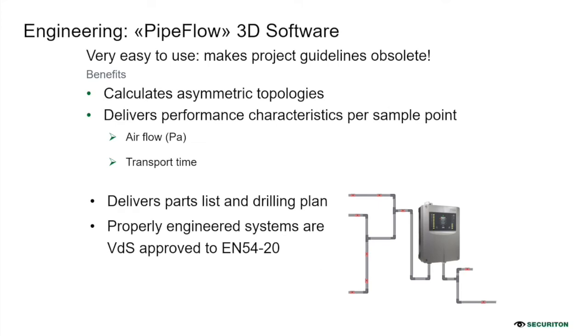During the question and answer session, you asked about software. We have software which calculates the pipe length, the airflow, transport time, number of holes and size of holes. Depending on the individual hall, we can design a customized system based on its requirements. The software is capable of designing systems appropriately and is also approved by the competent authorities. The results are EN and VDS approved.